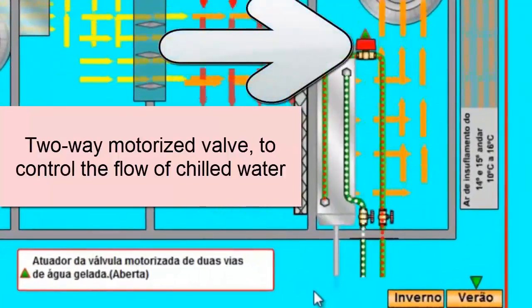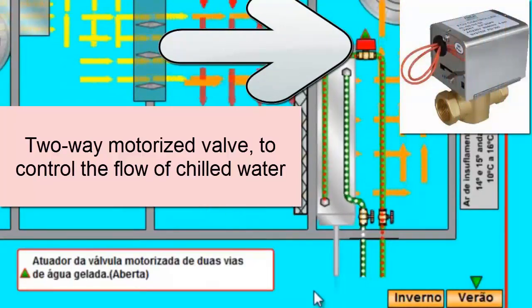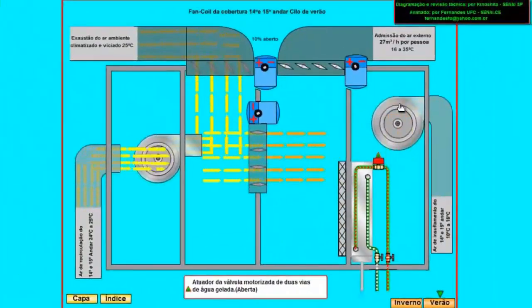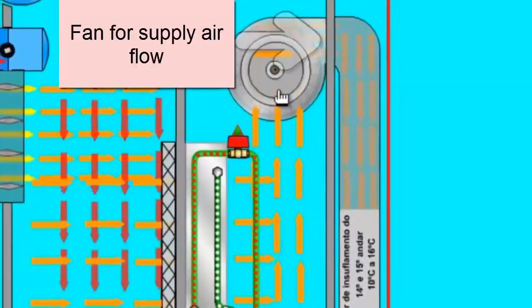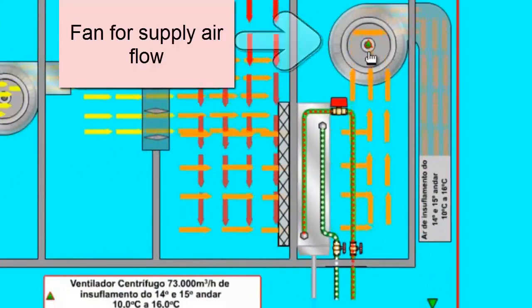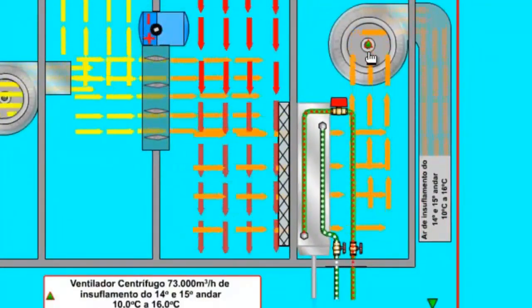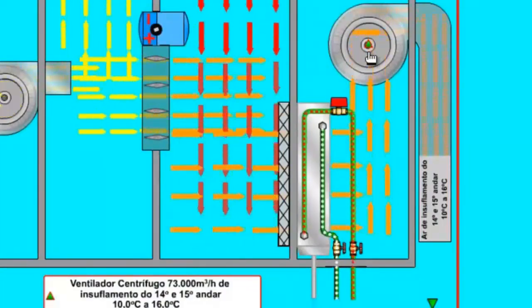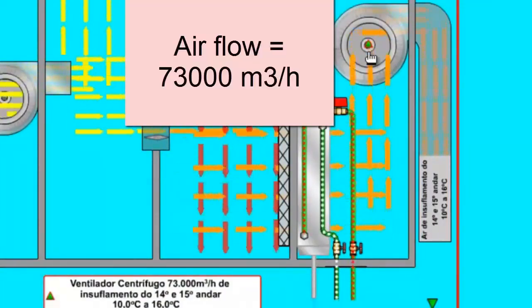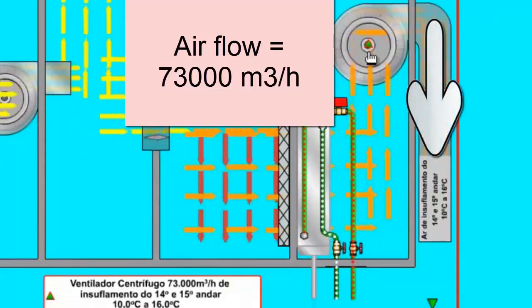2-way motorized valve to control the flow of chilled water directed to the coil. Supply centrifugal fan — it is in charge of supplying the air flow with the necessary pressure so that it reaches all the grills of the premises. The air temperature should be between 10 and 15 degrees Celsius. This fan has constant speed, and at this moment it manages a flow of 73,000 cubic meters per hour of air.